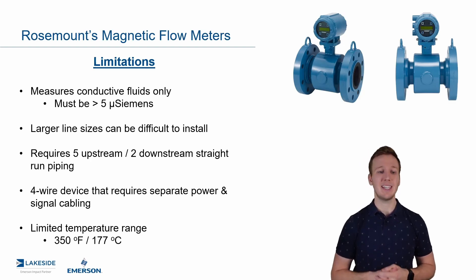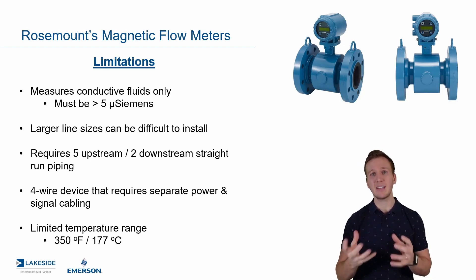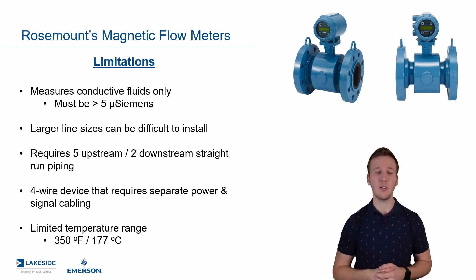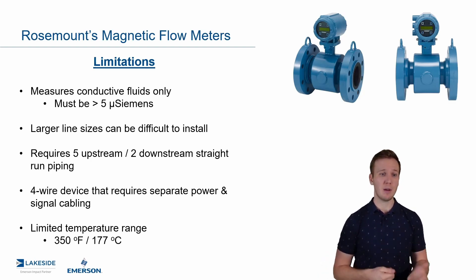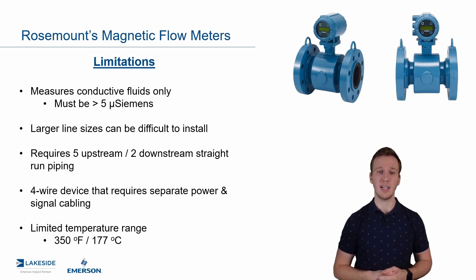Lastly, there are limited temperature ranges up to 350°F, and that's because we typically have a plastic or rubber liner on the internal of the magnetic flow meter. Beyond that temperature you would melt the liner and potentially also damage the electronics if it's integrally mounted, like the unit above me here.